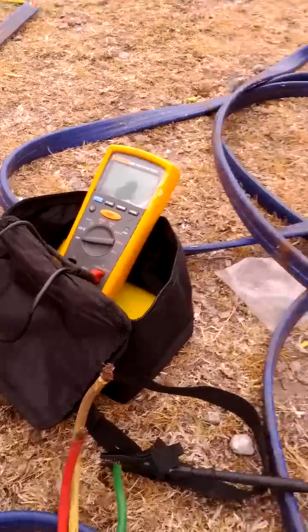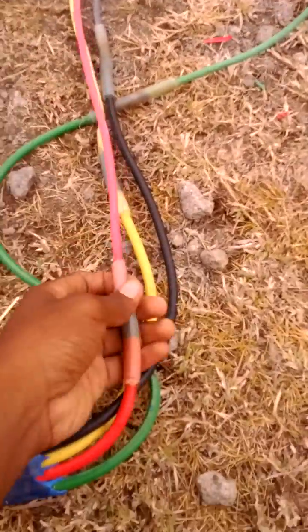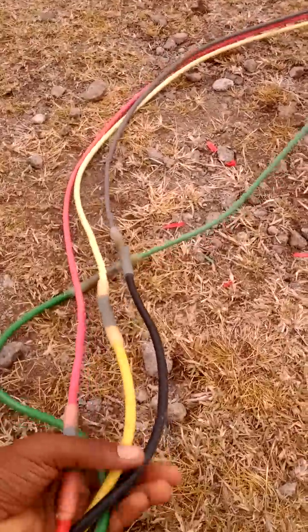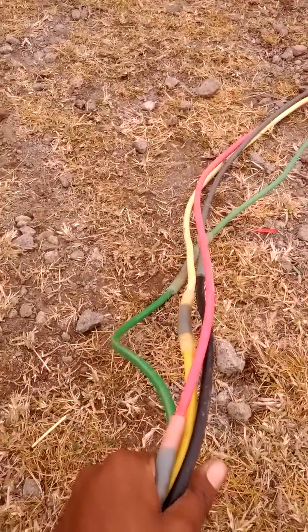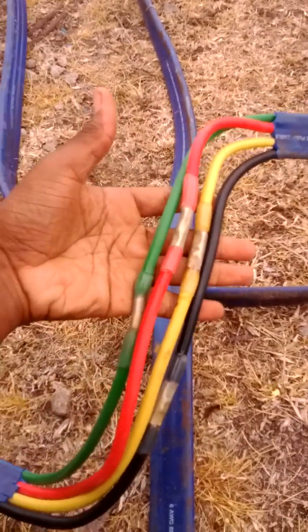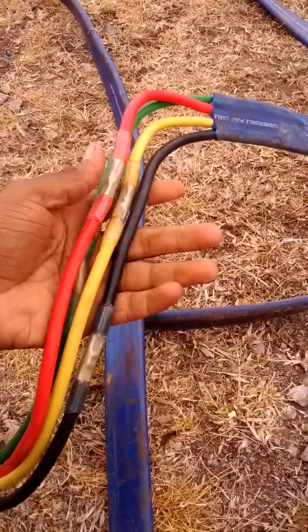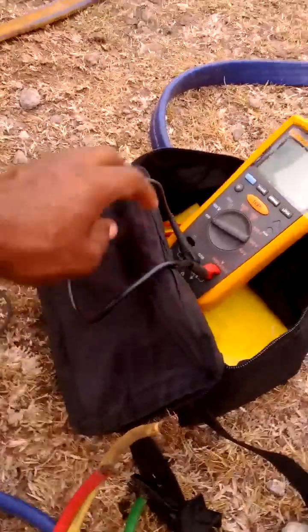On this wire I have two joints. This one right here — you can see my phases are all joined up — that's one joint from the motor to the start of the cable. And I have another one here. What really happened is the cable got a bit eaten up, punched up, spliced, and cut up coming out of the well, so we had to splice it. So we have two splices on this cable. Now I'm gonna go straight to the test.